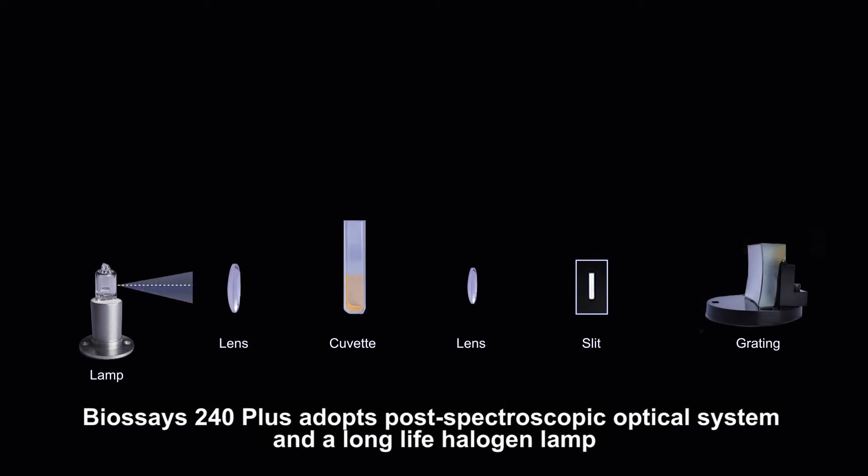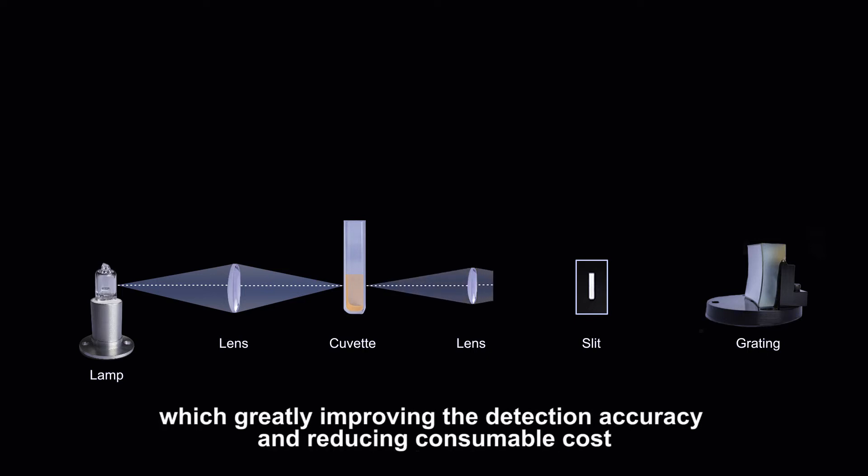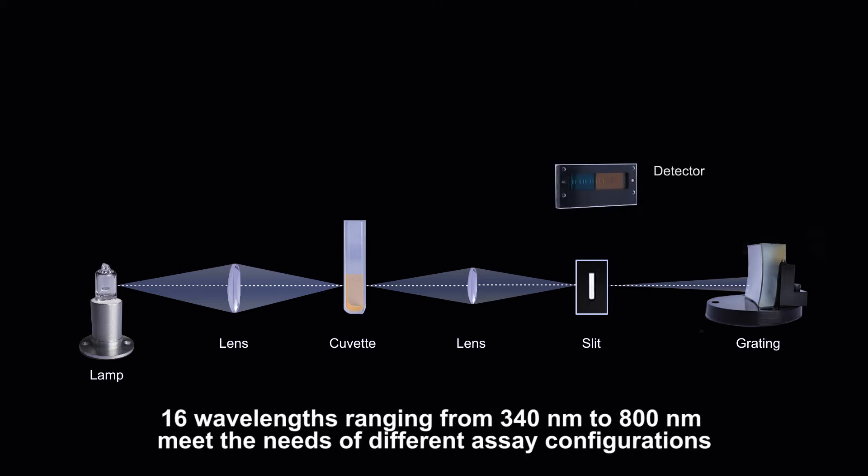Biossays 240 Plus adopts post-spectroscopic optical system and a long-life halogen lamp, which greatly improves the detection accuracy and reduces consumable cost. 16 wavelengths ranging from 340 nanometers to 800 nanometers meet the needs of different assay configurations.